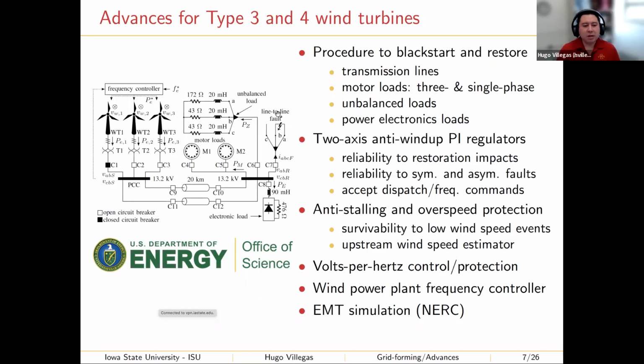For example, here I'm depicting a line-to-line fault event. During the Panhandle disturbance, line-to-line faults led to the disconnection of more than 1 gigawatt of wind power. The good thing about these two-axis anti-windup PI regulators is that they can accept dispatch and frequency commands. During this work, it was also necessary to develop an anti-stalling and overspeed protection for the wind turbine. So one part is about controlling the converter that is interfacing the grid, and another part is about controlling the wind turbine, which is the primary energy resource.